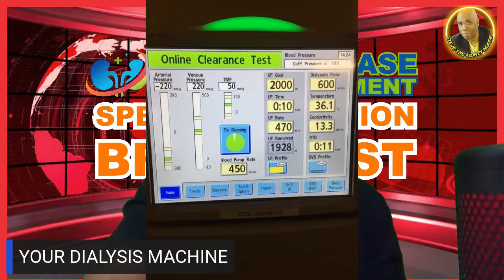Also, it's extremely important to check that the venous and arterial chambers are filled to the appropriate level. And that's on these machines right here, that's these levels right here. The arterial and venous should be filled up. Also, the heparin pump. The heparin pump should be checked to make sure it's delivering the right amount of heparin.